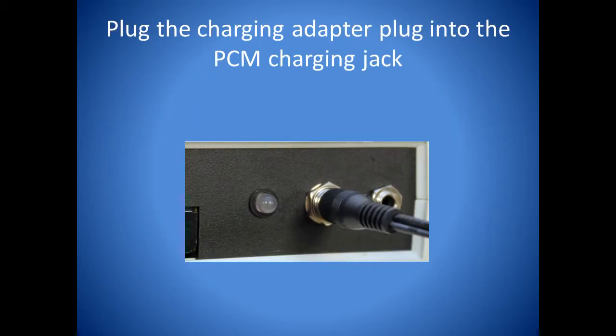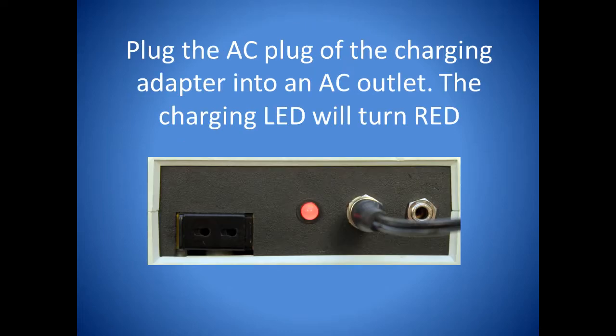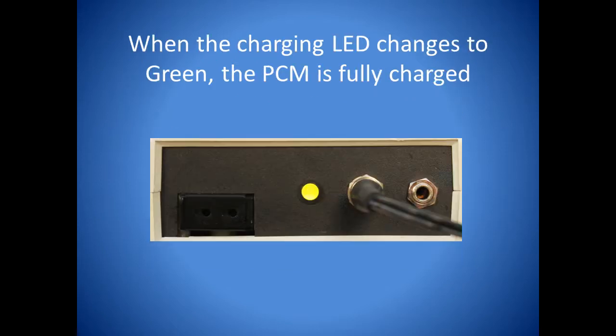To charge the power control module, plug in the end of the charging adapter cable that comes with the power control module with the round 2.5mm plug into the charging jack on the power control module. Plug the other end of the charging adapter into an AC outlet. The charging LED on the power control module will turn on and it should show red. When the charging LED on the power control module turns green, the power control module is fully charged and ready to use.